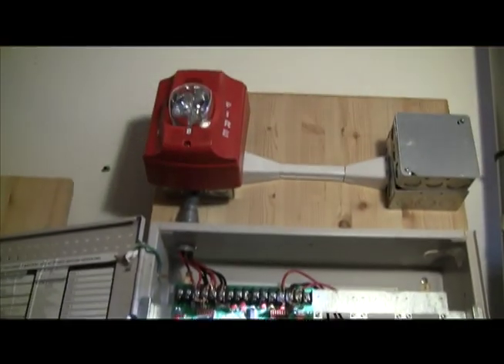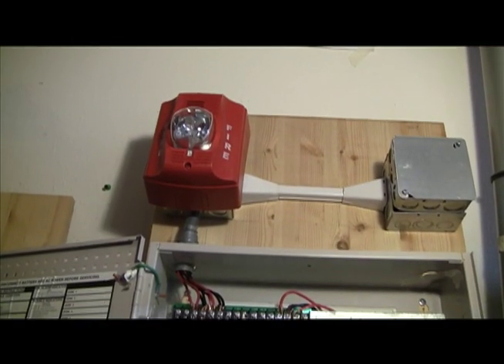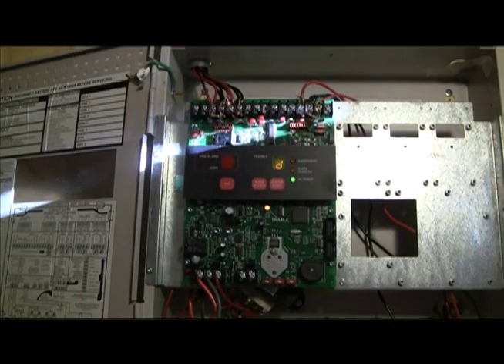For the alarm, I have a System Sensor P4R, and the panel is coding it to fast march time.